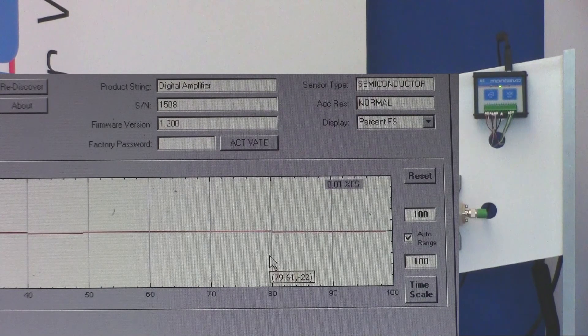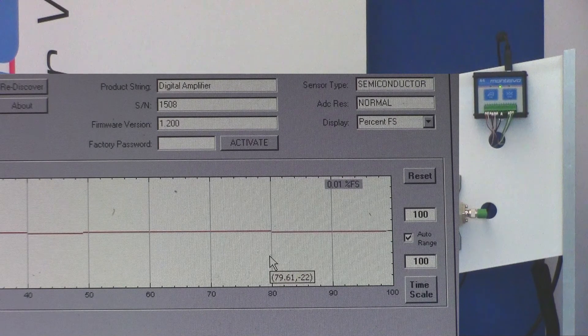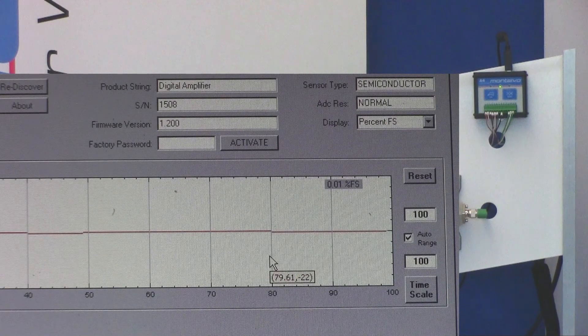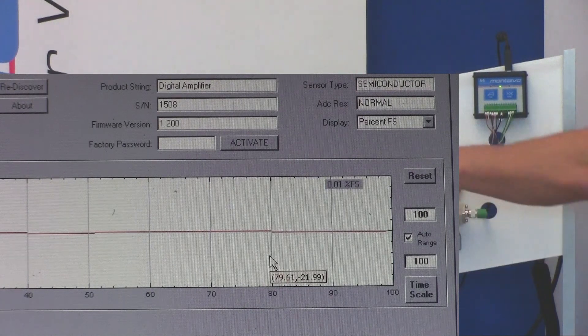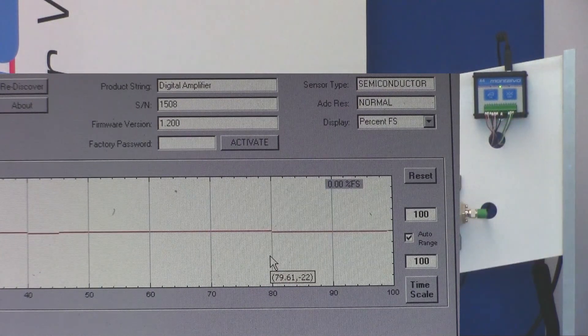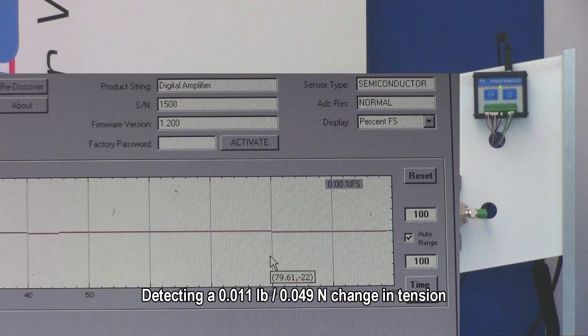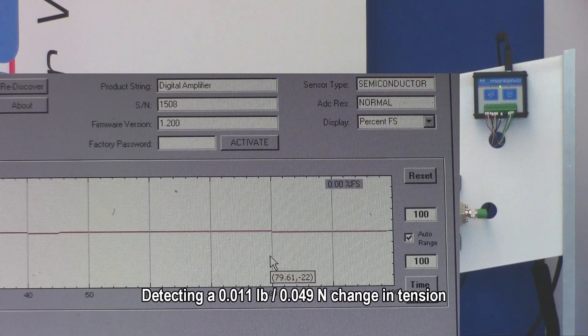Where 50 pounds is the maximum load rating, I am accurately, precisely, and repeatedly sensing changes to 0.022% of the load rating, or a mere 0.011 pound change in tension.